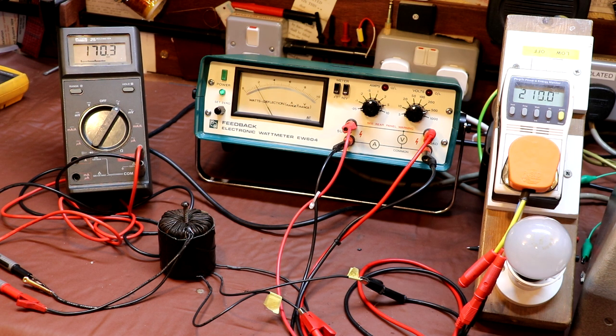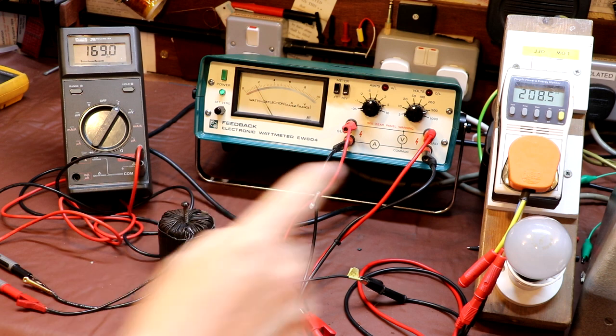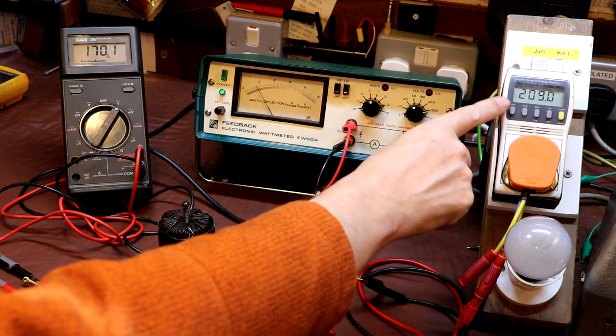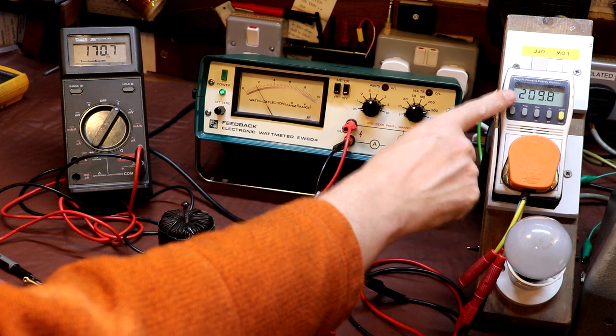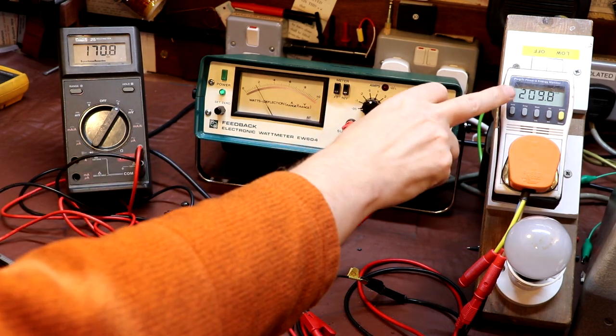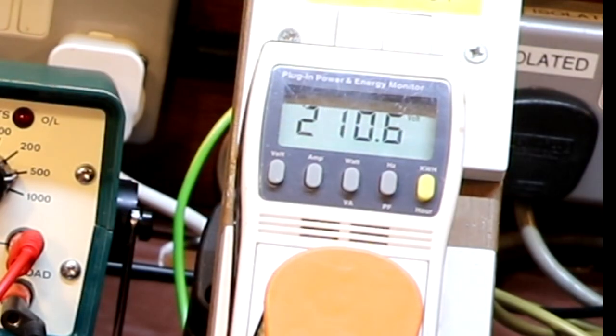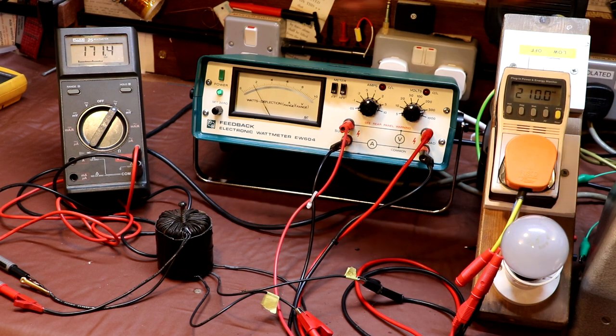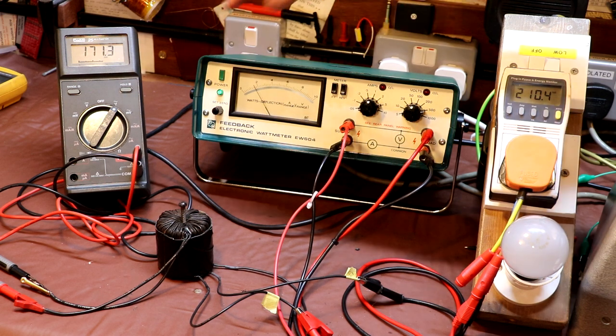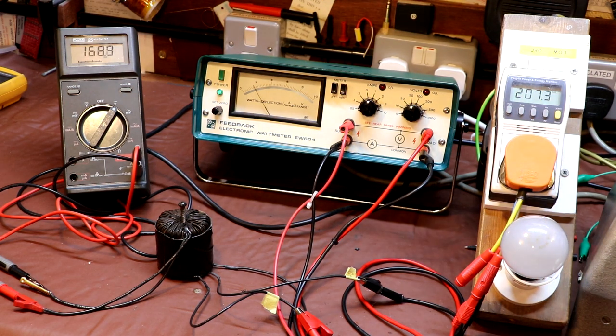Then we're going to put a load across the transformer, but we have to draw the transformer's rated current, and we believe that the rated current for this transformer is around 20 milliamps. But when you're doing the loaded test and the unloaded test, it's very important that we keep the primary voltage the same. So I'm going to adjust the variac here to keep that set as close to 210 volts as possible. Just tweaking up the voltage very slightly. I'm afraid my mains is going up and down, but we'll get it close enough. So we've got about 210 volts on the primary. We just need to make a note of this now. We've got 171 volts on the secondary, so write that down, 171 volts.